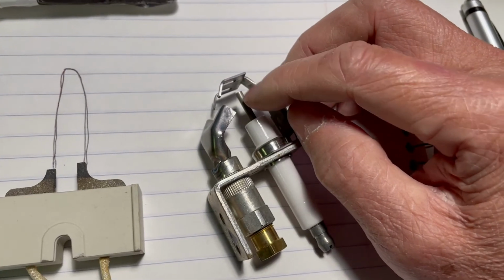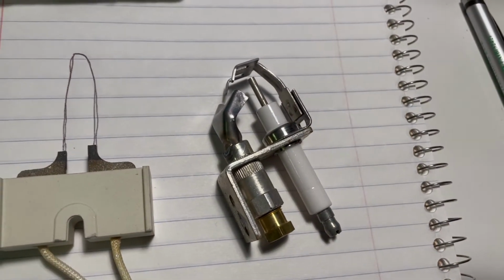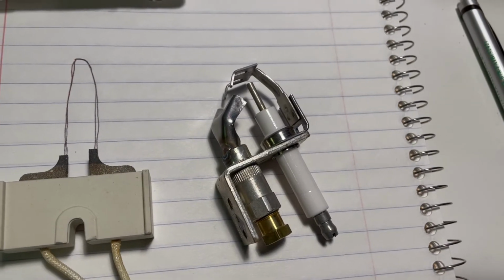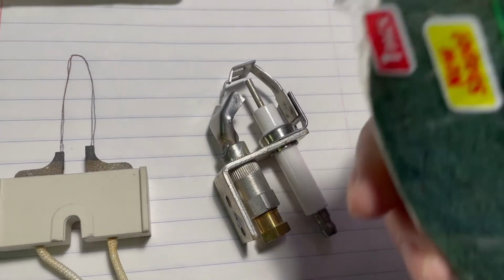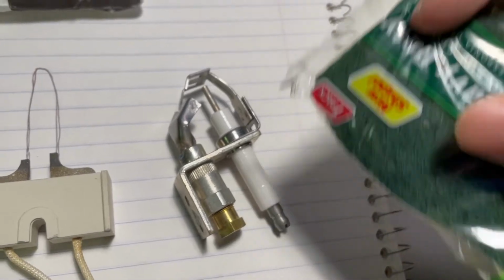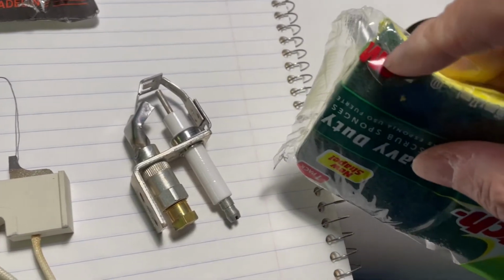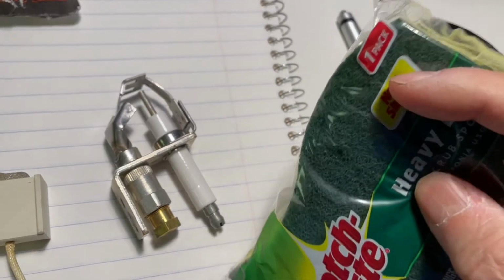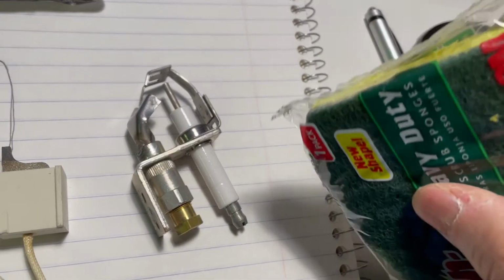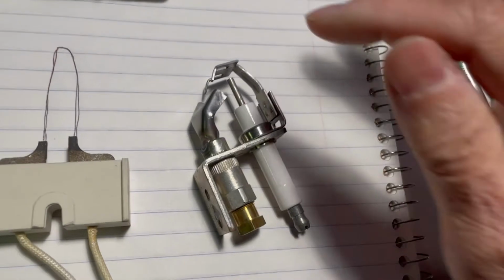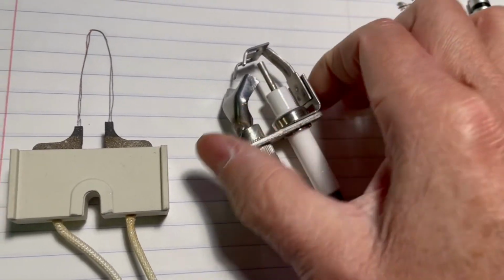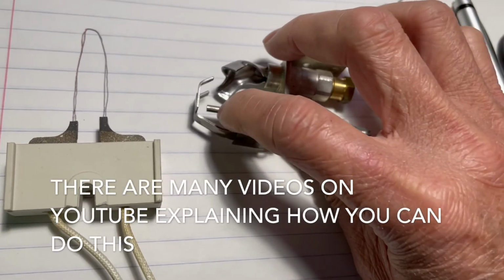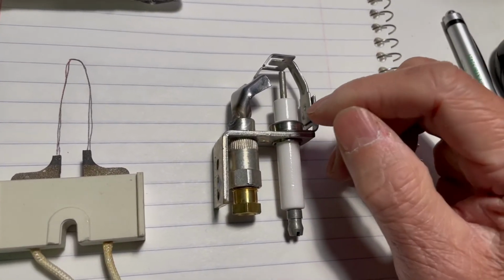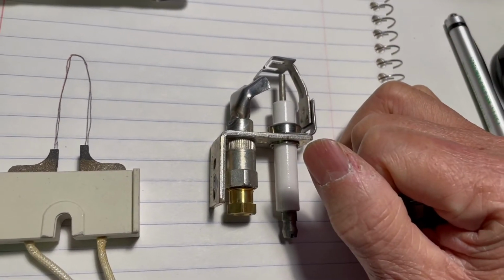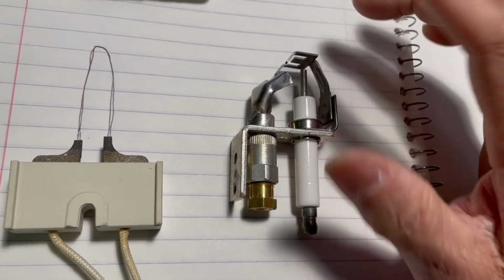So over time it would have some contaminants on it, and what they always recommend is to clean it. And you can use a scrubber like this, except don't use the green one. 3M makes the blue one, which is less abrasive. And then you just slightly rub the length of this rod here. This is a flame sensing rod. And then the ignition problem would be solved.